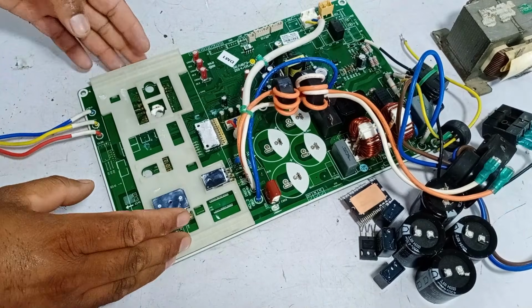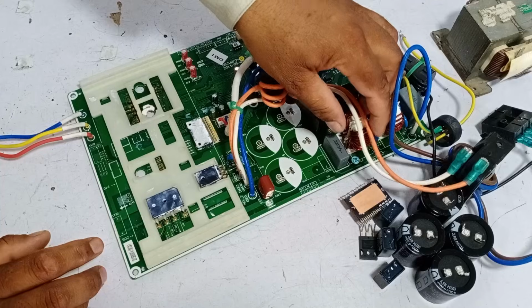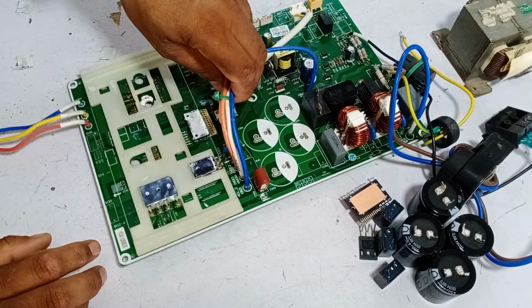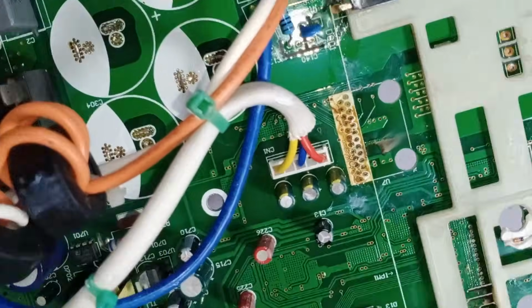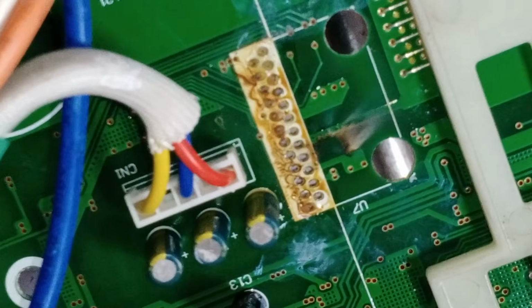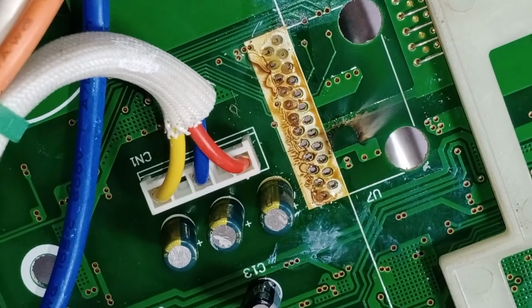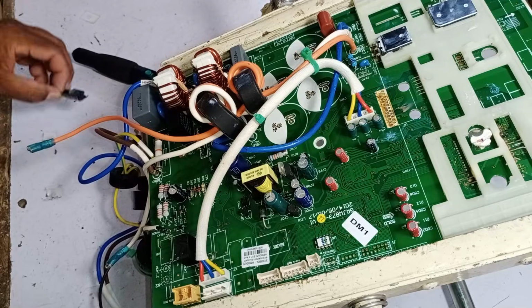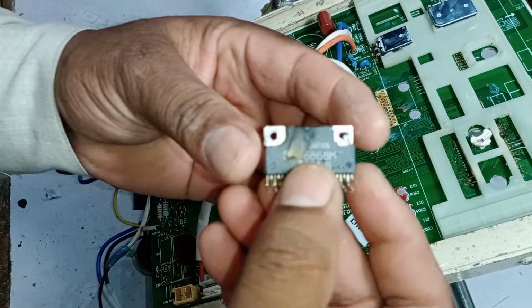I've already removed the high side components, and I also checked the low side - there doesn't seem to be any problem. I've found the fault in this circuit. Look, this IPM was burst. It burst from the bottom, so it wasn't physically visible from the top. Moreover, it caused a short circuit across the entire circuit board.